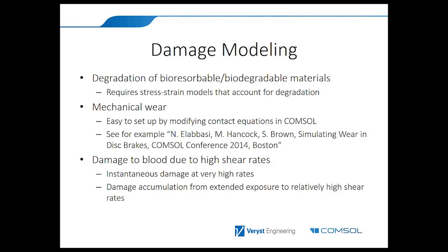And the last item is damage to blood. Blood cannot take a very high shear rate. So again, if the shear rate gets very high instantaneously, there will be damage. Damage can also accumulate for extended exposure time to a certain shear rate, and we need to capture that.